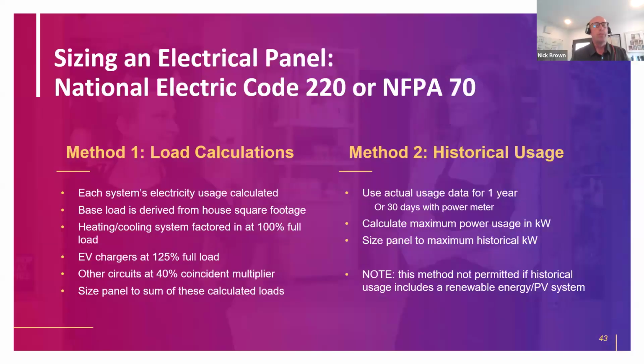The National Electric Code provides two pathways to size an electric panel. Method one is load calculations; method two is historical usage. Load calculations, which we'll walk you through in a spreadsheet tool in a minute, take each system's maximum electricity usage. It calculates a base load, things like lighting and receptacles based on square footage. It takes the full amount of heating and cooling power, because if that HVAC system has been sized right for your house, at one point in the year it should run flat out. So we need to reserve at least that much power. EV chargers get factored in at 125% of their full load, which is why Robert's focus on not oversizing those EV circuits is so apt.